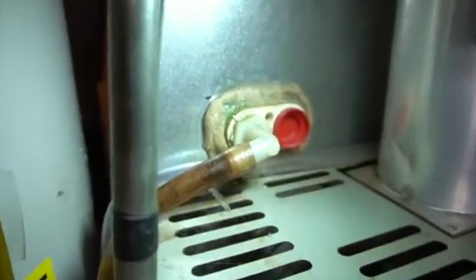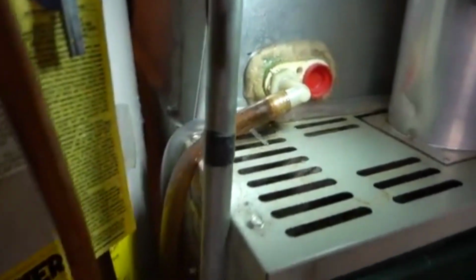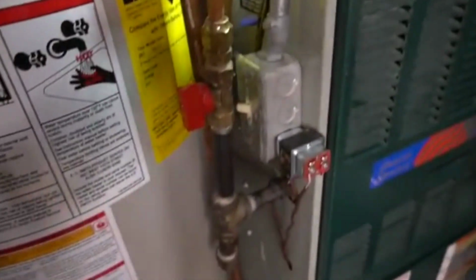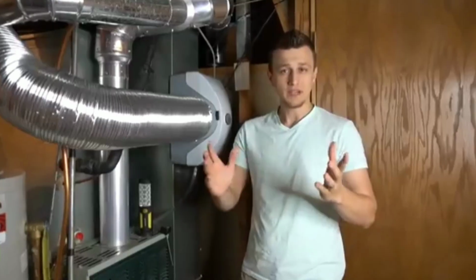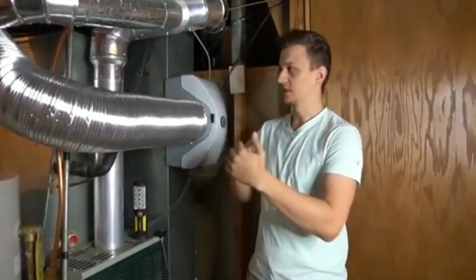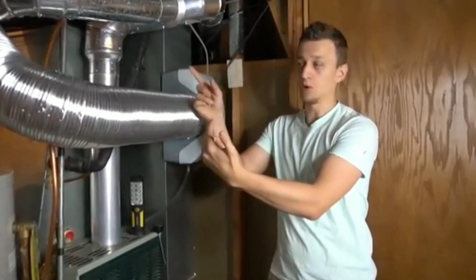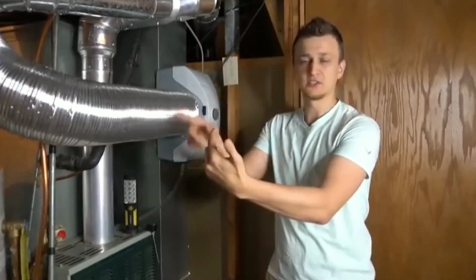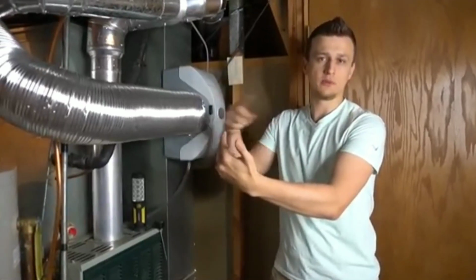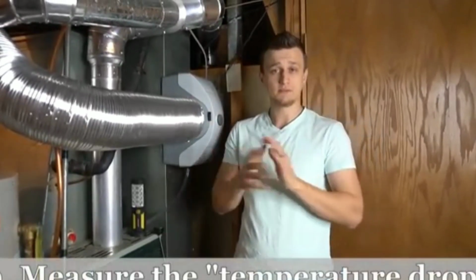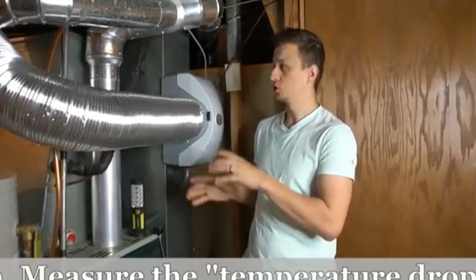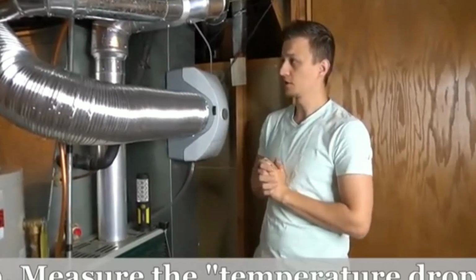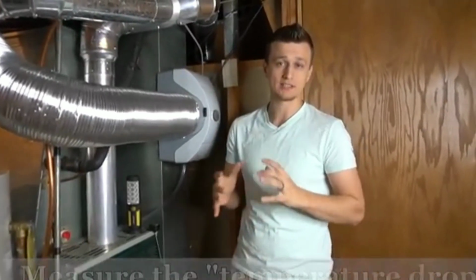and just runs to your floor drain, your sump pump, or whatever you got going, or maybe even a drain pump. So basically the way the air conditioner works is it's pumping that Freon from outside to inside in a constant loop. It's just going back and forth, back and forth. So maintenance tip number 9 is to check temperatures on your air conditioner to make sure it's working correctly.